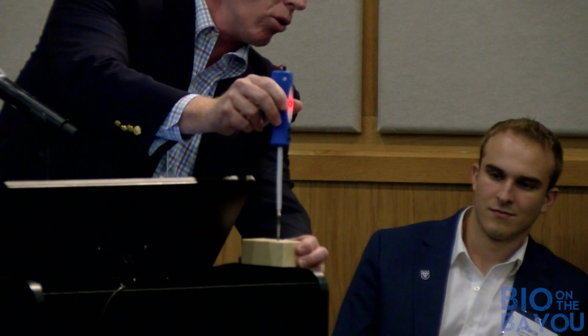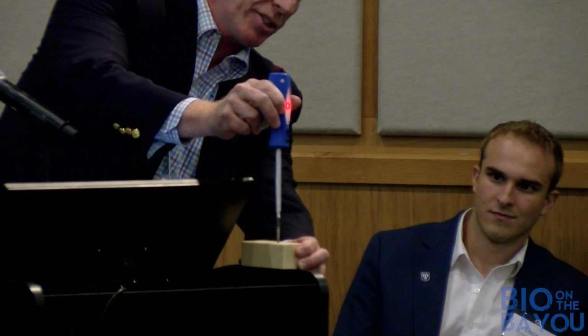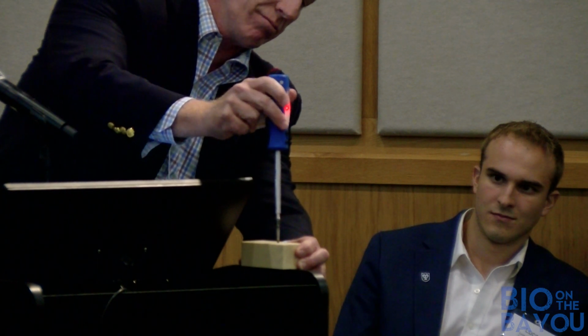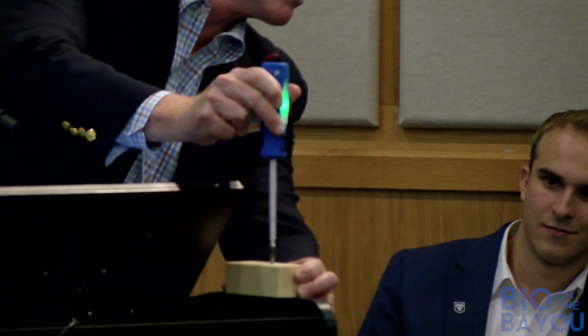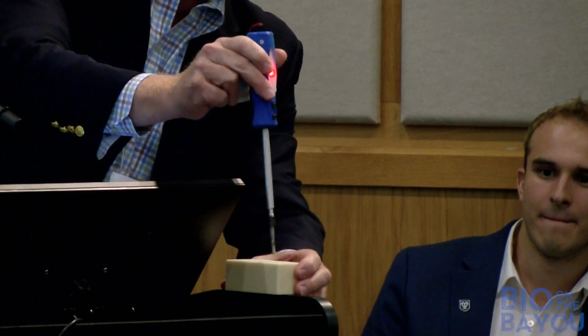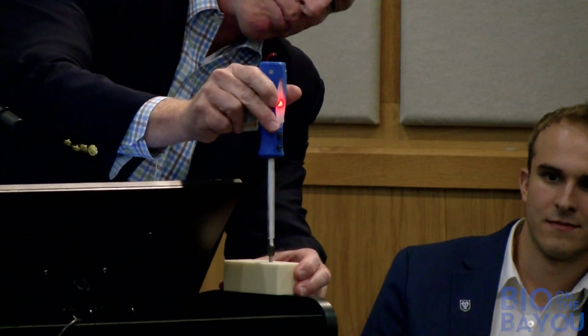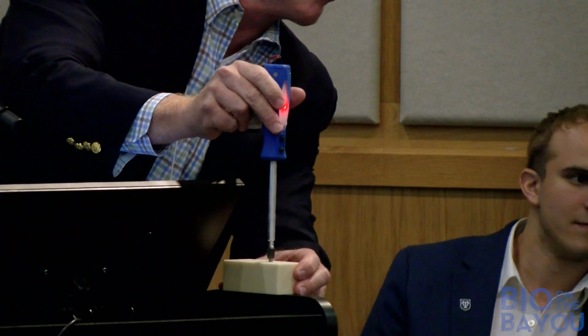The surgeon simply creates the hole like they're getting ready to put the screw in during surgery, and they would just take the extra step of pushing the device in. And they get a green light, meaning this is good bone, so they can just put their screw in and continue the case. If they run across some bone that's not so good, they push the probe in. It's red. So this is not good enough bone. Then they can consider some alternatives for the case. Maybe it's so bad and it's in every vertebra in the spine, because you can test every single screw hole location. And at that point, they might abandon the case and say it's not worth the risk of doing a case.